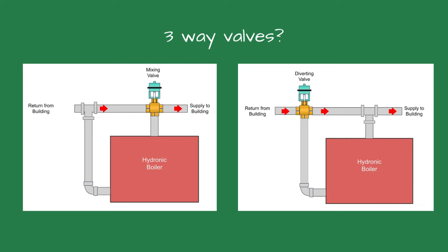Check the piping you are connecting to — is there a 3-way valve? An incorrectly installed 3-way valve could damage the boiler by thermal shock. Most hydronic boilers are designed for a 20-degree delta T, or temperature rise through the boiler. If it is greater than that, it could destroy the boiler.